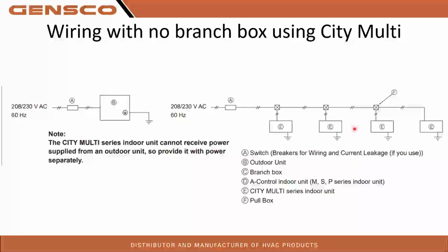So what ends up happening is when your heat pump powers on, one of the first things it starts to do is start looking for all the indoor equipment that's attached to it. If it doesn't see all that equipment pretty quickly, it just stops looking for it, it gives up. So that's why we need to make sure to have all of our indoor stuff powered on before that heat pump gets turned on. This includes power cycles or anything like that in the future you may be doing. Just remember, make sure your indoor equipment is powered first.